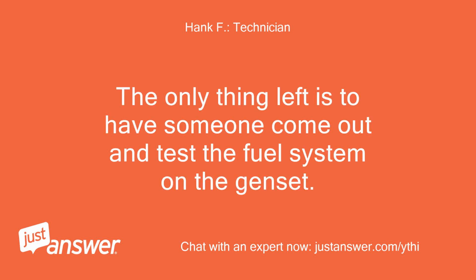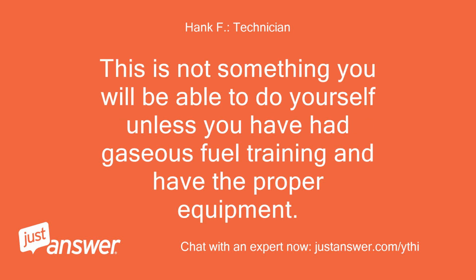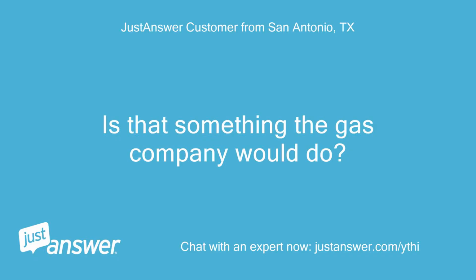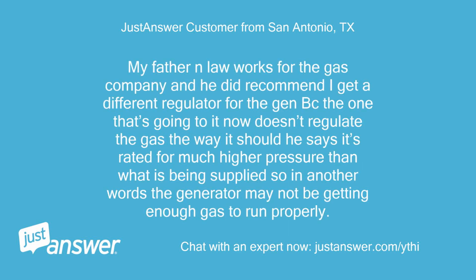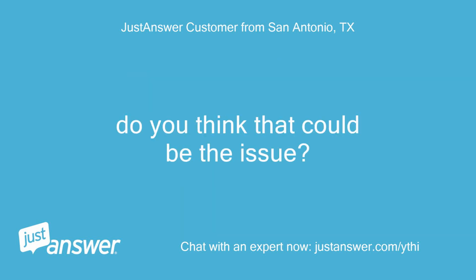The only thing left is to have someone come out and test the fuel system on the genset. This is not something you will be able to do yourself unless you have had gaseous fuel training and have the proper equipment. Is that something the gas company would do? My father-in-law works for the gas company and he did recommend I get a different regulator for the generator. The one that's going to it now doesn't regulate the gas the way it should. He says it's rated for much higher pressure than what is being supplied, so in other words the generator may not be getting enough gas to run properly. Do you think that could be the issue?